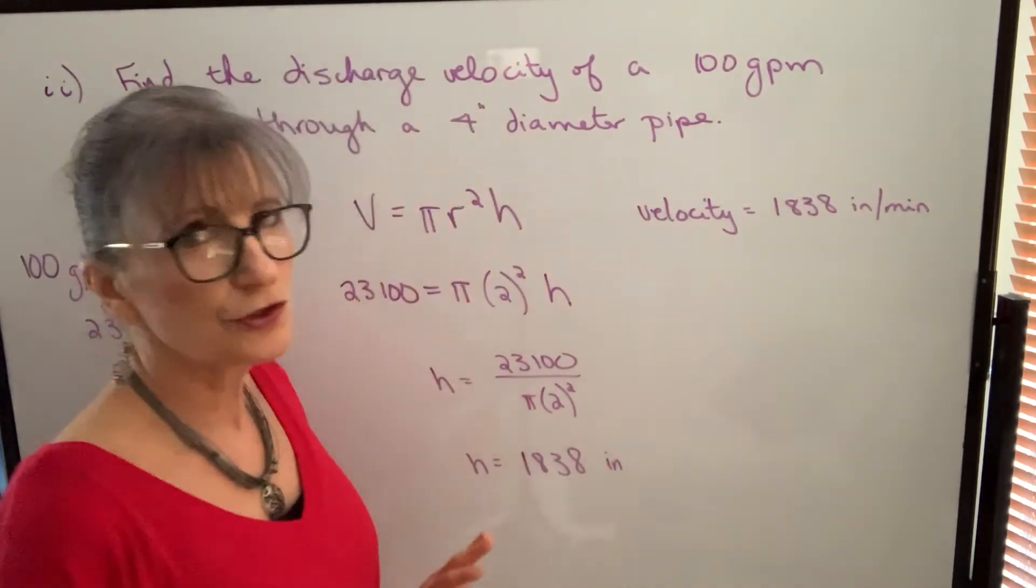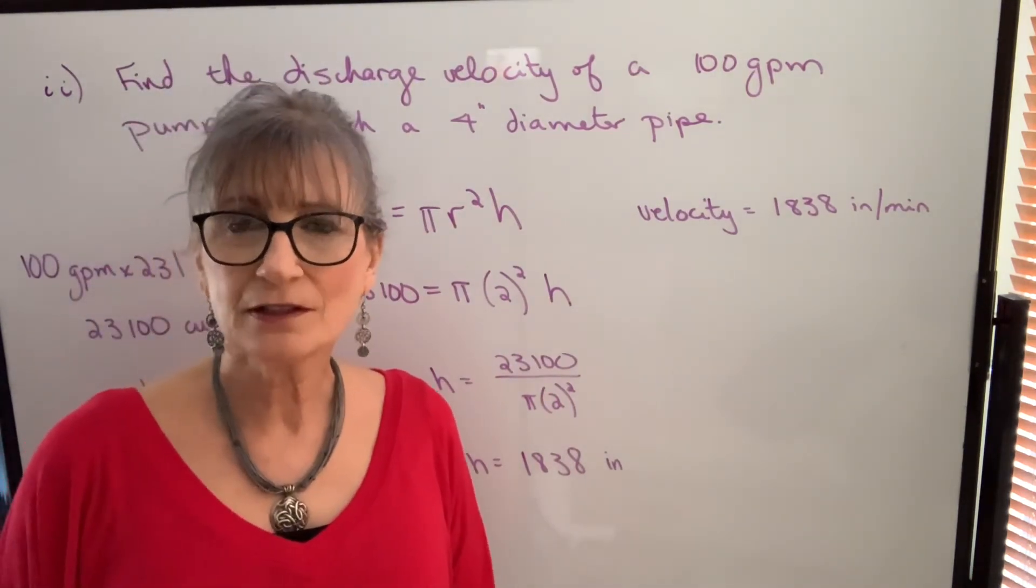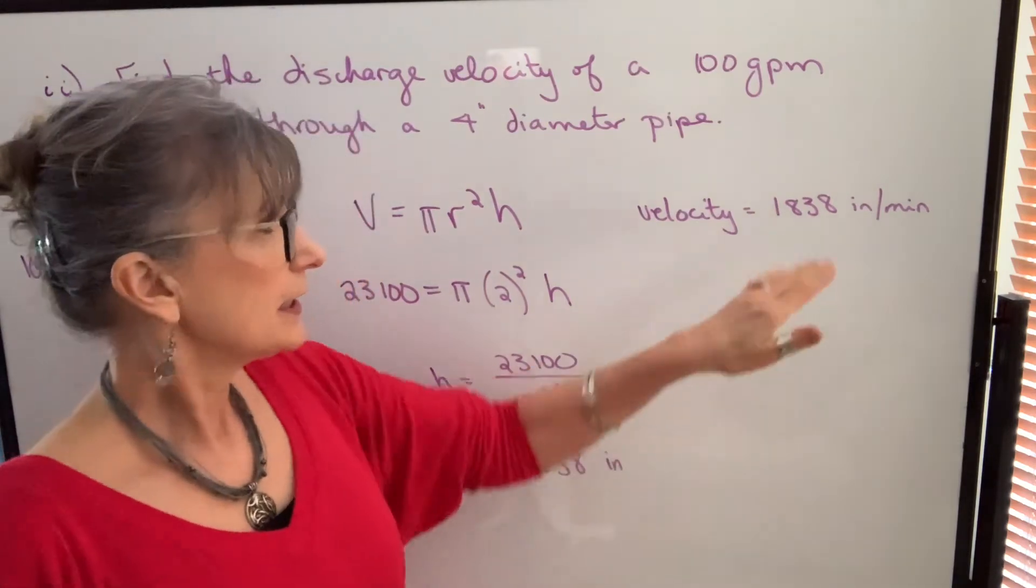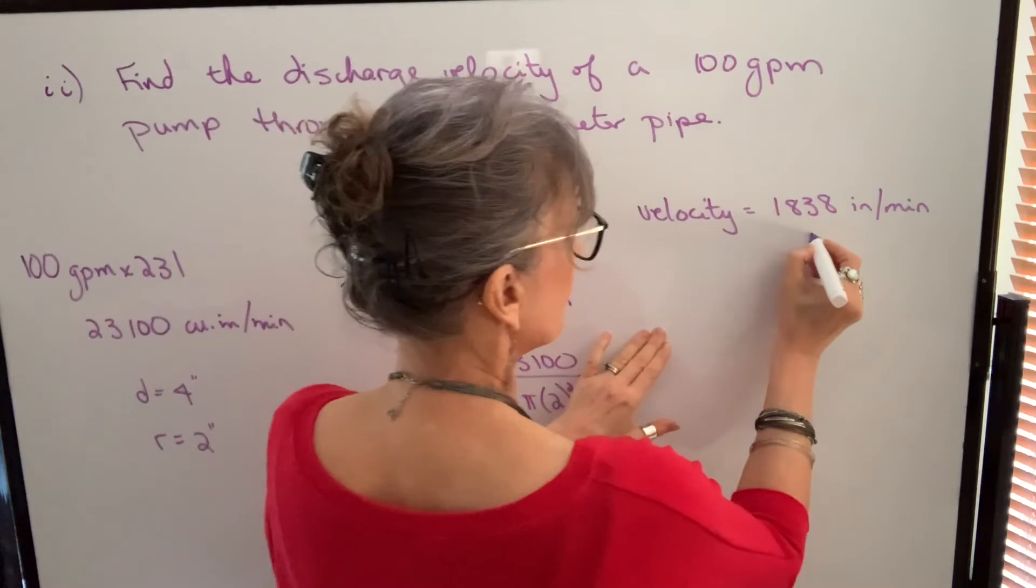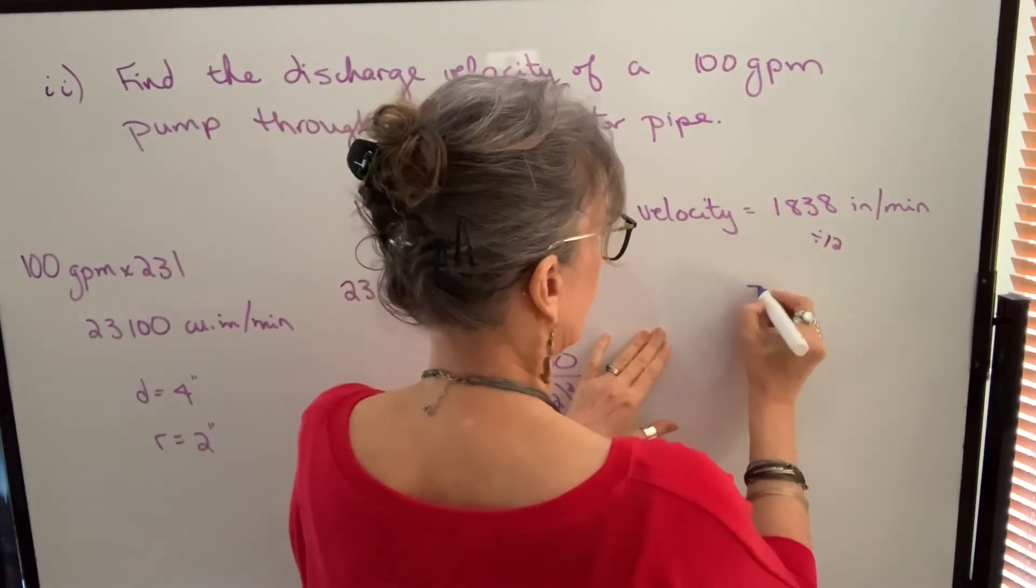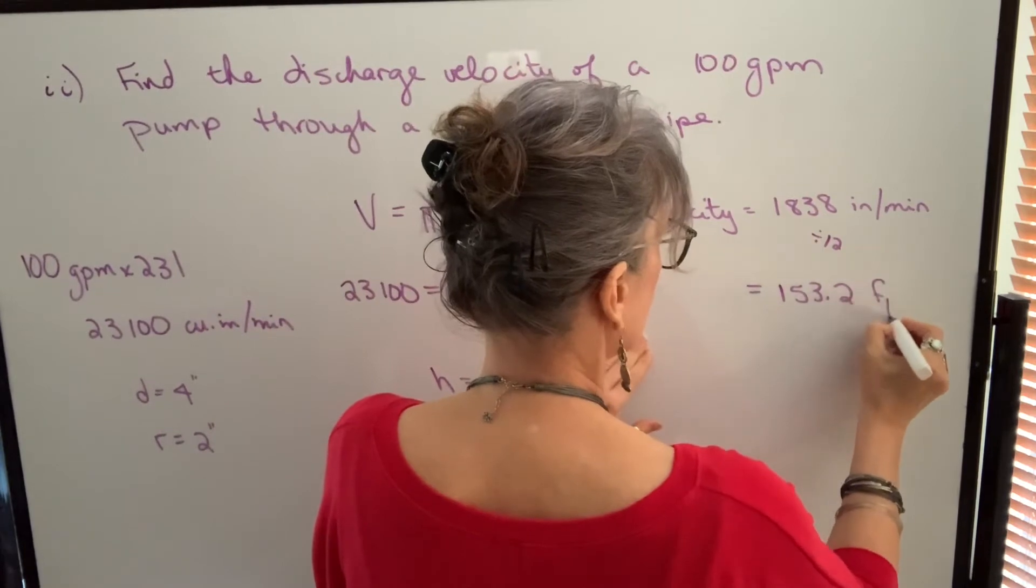So the discharge velocity will be 1,838 inches per minute. But that's not usually the unit that discharge velocity is expressed in. Usually it's either feet per minute or feet per second. Let's do one thing at a time. Let's change inches to feet. And the way that we do that is we divide by 12. So we get 153.2 feet per minute.